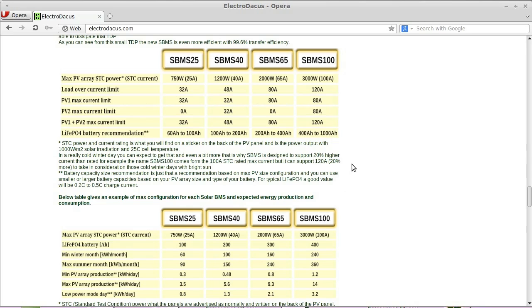But in winter, if you live in cold climates, maybe even minus 40 like here, then you can really get that amount of current and more. So I needed to leave a 20% margin. So if your solar panels are 25 amps total, maybe connected a few in parallel, you can be sure you will never run into the overcurrent protection limit, even if it's extremely cold and sunny with a perfect angle to the sun. You will not run into this problem. That's why I'm calling this SBMS 25, or 40, or 65, or 100 -- this represents the STC current value.